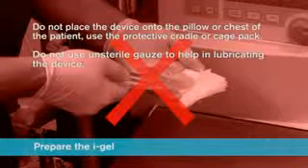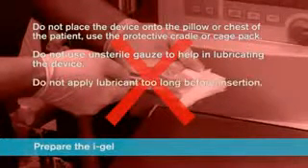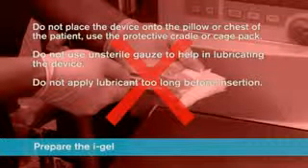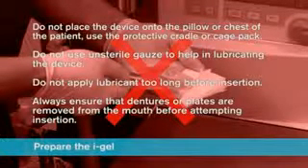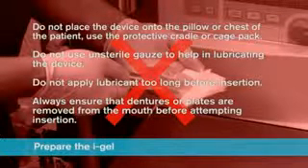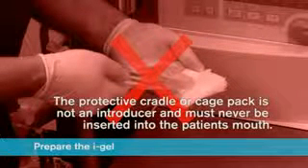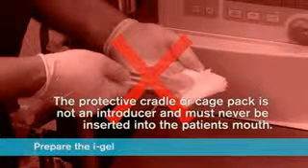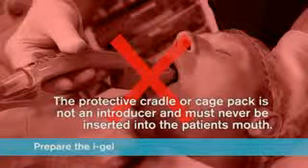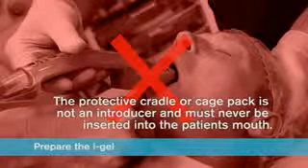Do not use unsterile gauze to help in lubricating the device. Do not apply lubricant too long before insertion. Always ensure dentures or plates are removed from the mouth before attempting insertion. The iGel must always be separated from the protective cradle or cage pack prior to use. These are not introducers and must never be inserted into the patient's mouth.